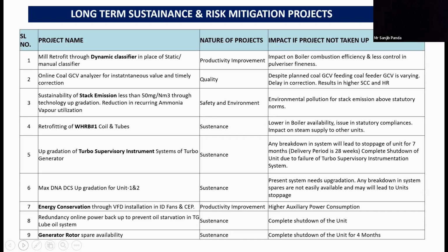And third is the sustainability of stack emission. As we are aware, the limit is 50 as per the regulatory year, and because of the variance in the type and quality of coal, there is a real challenge in maintaining the limit below 50 milligram per Nm cube. So there is a thinking of going for reducing this through upgradation of technology in the ESP. Then retrofitting of WHRB coils and tubes to increase its reliability, which presently we are doing in WHRB2.